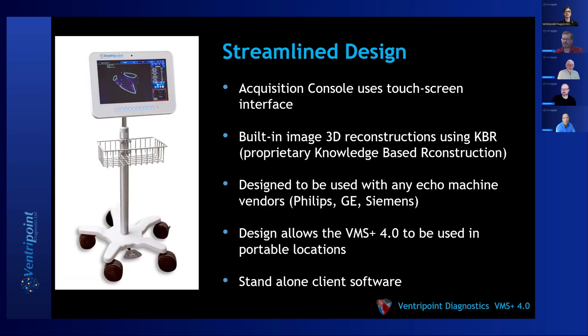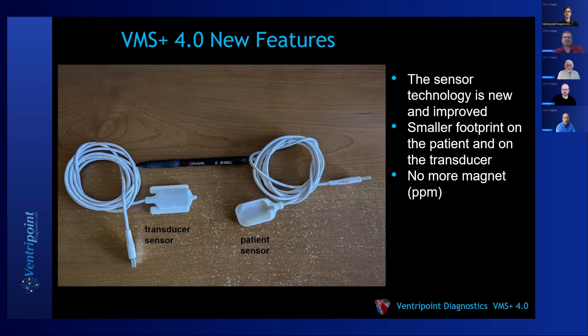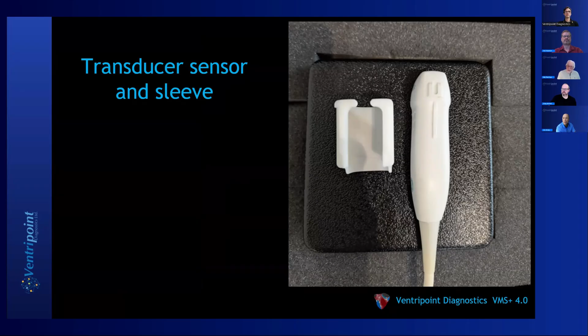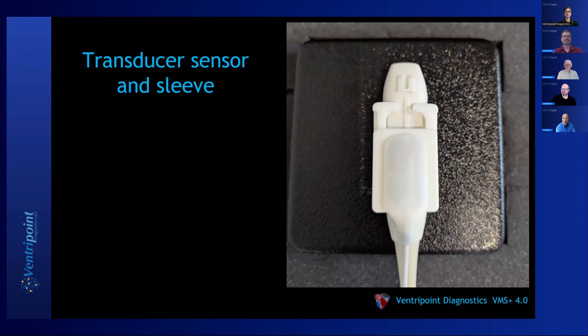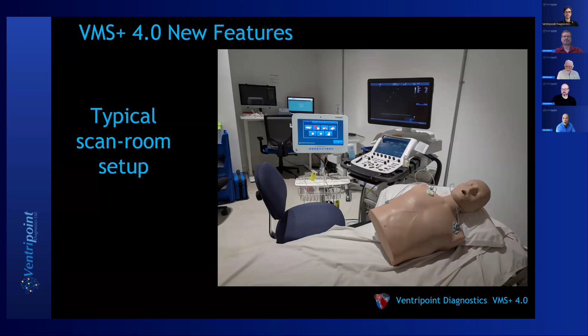The other key components of our system are the transducer sensor and the patient sensor. These sensors help us generate position information of the image or the cine that's being acquired. This is an example of our 3D printed sleeve that goes on top of, in this case, the GE M5SC transducer. It fits inside, and then we slide our transducer sensor right on top. And here's a typical setup of an imaging room. The echo machine, the sonographer and the patient all live in the same place. We're not asking for anything different. And right beside the sonographer would be our console.